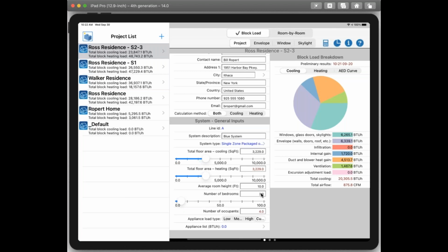Here we enter the number of bedrooms, and based upon that it actually calculates the number of occupants—as I increase the bedrooms, it increases the occupants, simply adding one each time. Occupant load is important because, especially with a large number of people, they contribute not only sensible loads to the space but also latent loads.